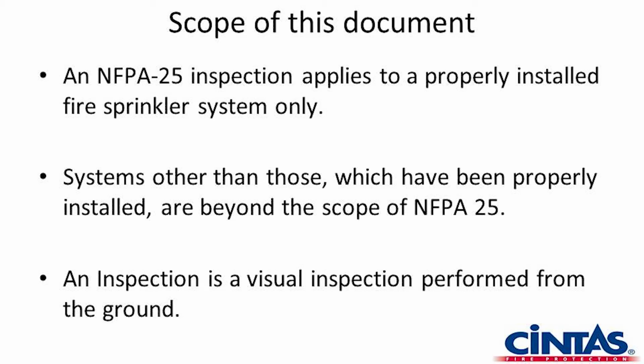They will send in deficiencies that say we need to add sprinkler heads or we need to move sprinkler heads. What this section of NFPA tells the inspector is to inspect and perform tests on the system that is there. We are to assume that it was properly installed at the time that it was installed, and that it was inspected by the authority having jurisdiction to be deemed correct. So we should not be making deficiency reports telling you that we're going to change the sprinkler system. That takes evaluation from a qualified sprinkler designer, an evaluation of the facility itself.